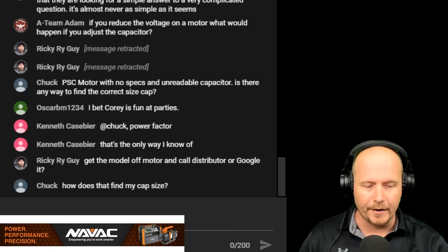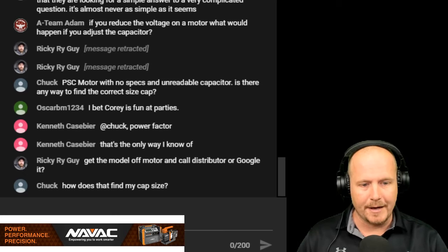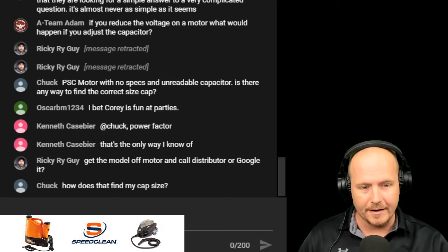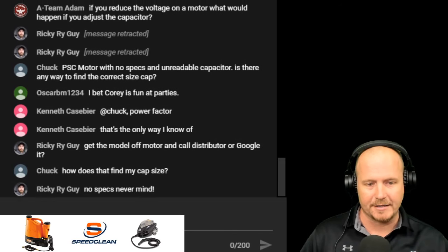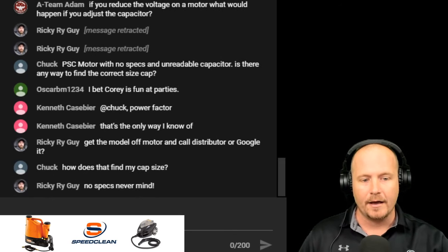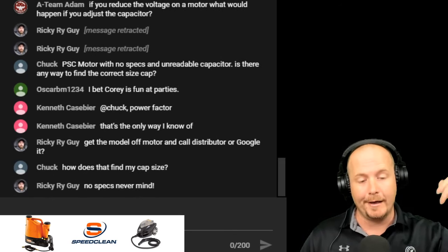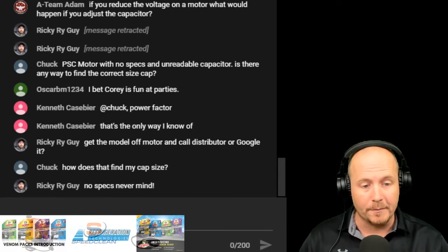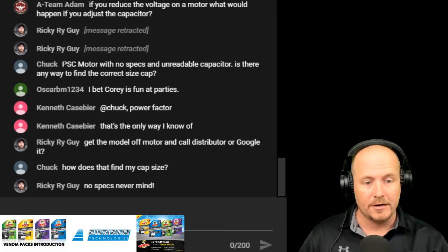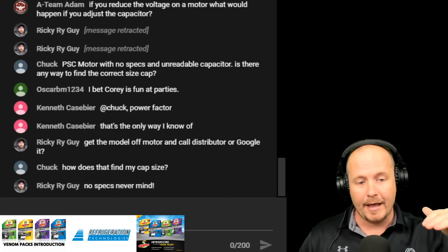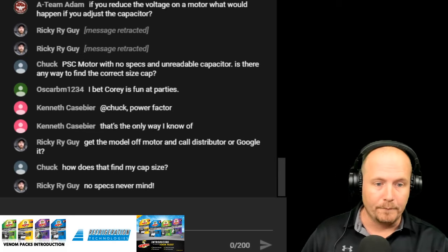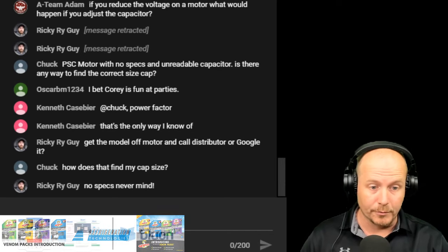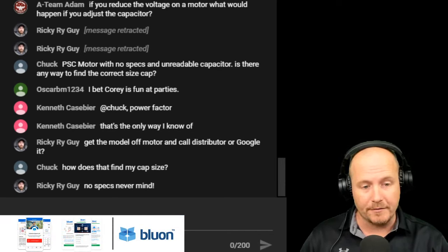But if you roll up on a 3-ton system with a bad capacitor on the compressor, and you can't read it, can't read the compressor for specs, and can't read the data tag, then put in a 35 microfarad capacitor and check your power factor and amperage. If your power factor is 0.98, 0.99, you're pretty darn close to what it's supposed to be.